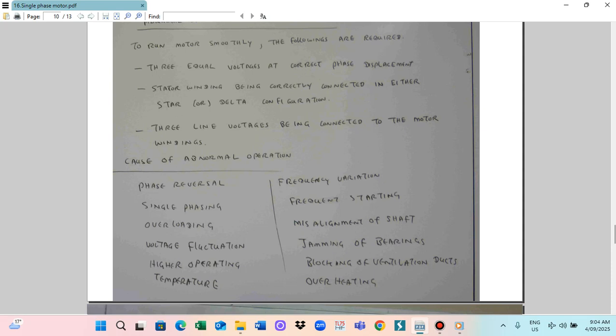We use a 230 volt system. But sometimes the voltage goes down to 200 volt, sometimes to 150 volt like this. So the most common victims are refrigerators. A refrigerator usually starts the compressor and then stops. Firstly, we notice the starting and stopping time is much quicker. Supposedly the compressor starts every 1 hour, but then you can see it at 30 minutes or 15 minutes like this. So this is a higher frequency of starting, and this is a bigger concern.